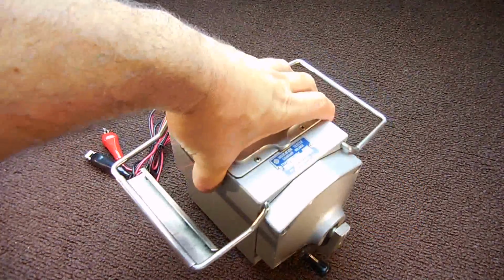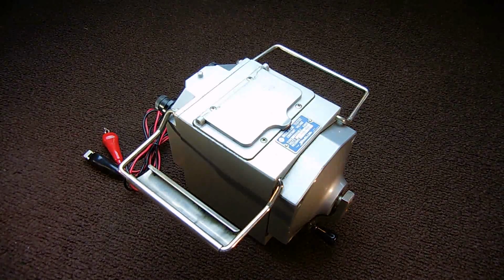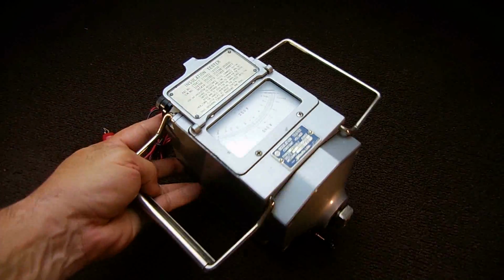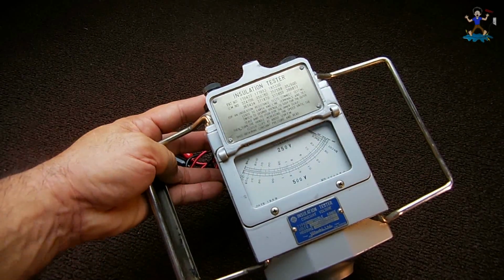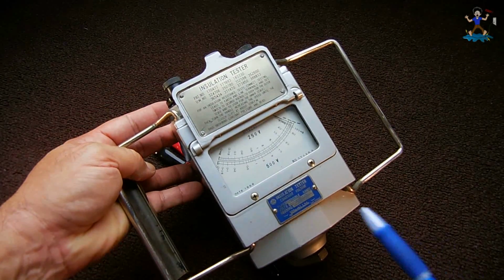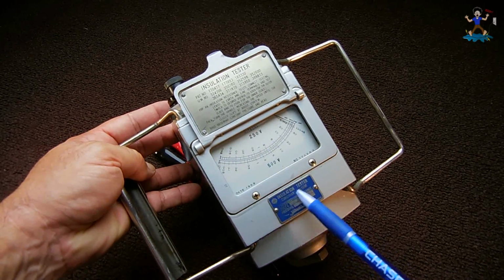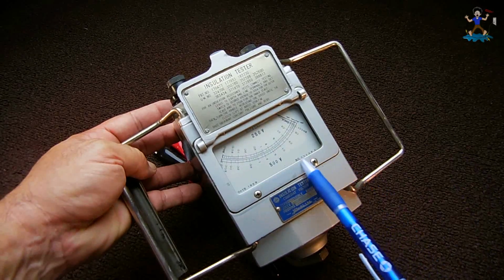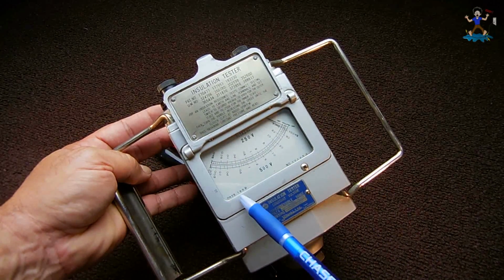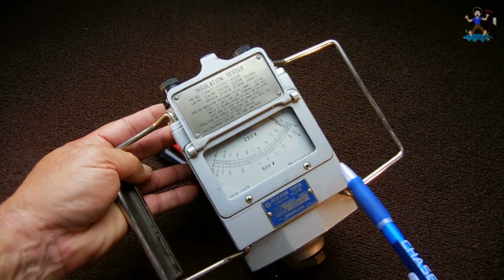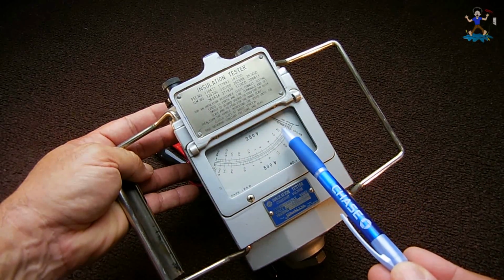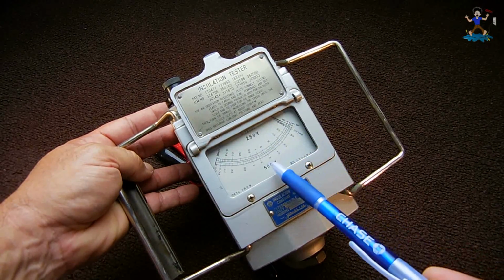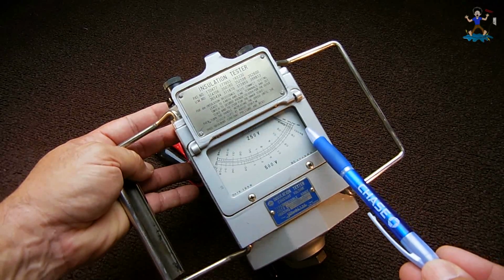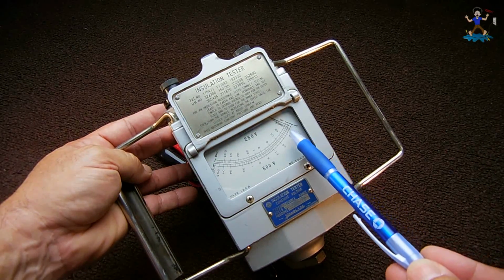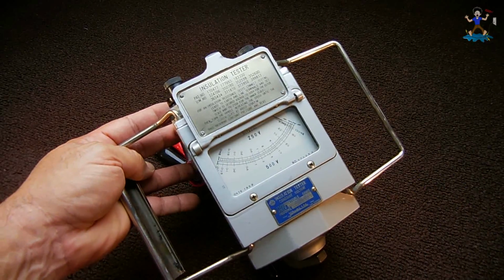Okay, let's go take a closer look at the crank generator. This one here, like I said, I found at a ReStore in my area, which is a Goodwill store. Open this up right there, and you can see there's a display. Move back just a little bit. That's a 250 volt scale. This has two settings. This is a Japanese made Hitachi unit. 500 volts here, and look when this thing was made, 1959. Incredible, really old. The scale goes up to 50 megohm at 250 and up to 100 megohm at 500 volts. There's the infinity line. Any readings above 100 would be probably into the thousands of megohms.